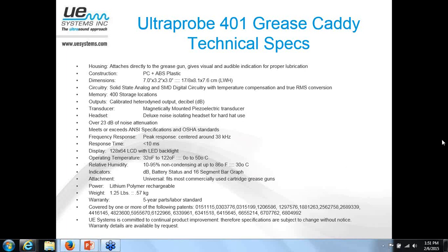So another question: can we use this to measure dB values while greasing bearings connected with remote lines? Yeah, and remember I mentioned that high frequency sound doesn't travel very far from the source. So the further we are away from that bearing, that sound is going to drop off, or that decibel level is going to drop off.